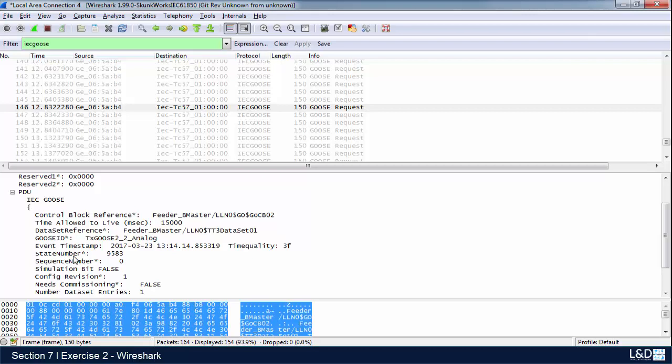Now the state number is something that every time a change occurs—whether it's we exceed a dead band or an analog signal changes states—the state number advances by one. The sequence number indicates how many times that signal's been transmitted. On our relays, the retransmission rate is three times, actually it's four times, so it starts with zero, one, two, and three.